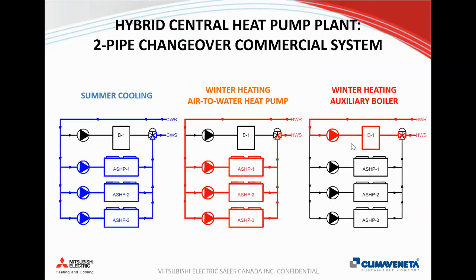So, just looking at a 2-pipe changeover system, just to visualize it, if you're using 1 or more heat pumps to meet the capacity at the design selection point, in summertime you have 1 or more units operating to meet the load and provide chilled water for the building. In wintertime, if you're operating off the air source heat pumps, you still have that backup boiler. And then if it's too cold for the cutout, or, because of an energy management strategy, if you want to go for costs and you don't want to operate the heat pumps below a certain COP, you can just switch over to the auxiliary boiler from there.